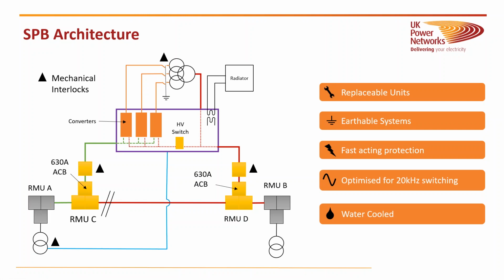And just so everyone knows, you're probably wondering what this HV switch is. Due to the design, we need to make sure that fault current isn't transferred from one side to the other. So this HV switch is a very fast operating switch. It operates in about 10 microseconds, and that makes sure that if there is a fault on either side of the network, externally to the SPB, it trips out and sends an intertrip to the two RMUs. And therefore limits the current.